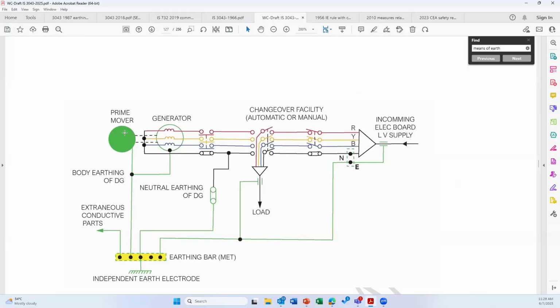You can see here the prime mover, the engine, and the alternator, the generator. The engine and the alternator body are connected to a common bus bar. Neutral is connected again through a link to the same common bus bar. The same common bus bar is used for connecting the extraneous conductive parts such as metal pipe, air conditioner duct, the rebar in the building, and so on. The incoming EB supply protective earth is also connected to the common bus bar. The load side protective earth is also connected to the common bus bar. The common bus bar is also connected to an independent earth electrode, which is called chassis earth. So basically, this picture has been there for 40, 50 years, since 1966, I believe.